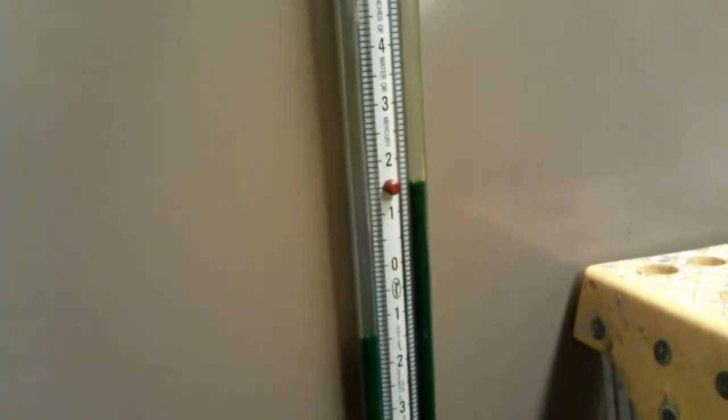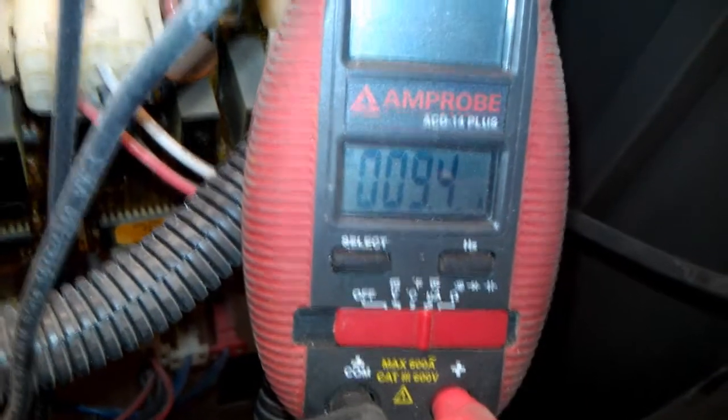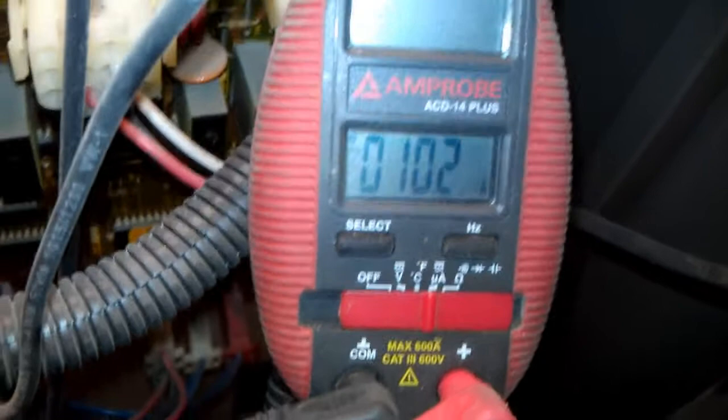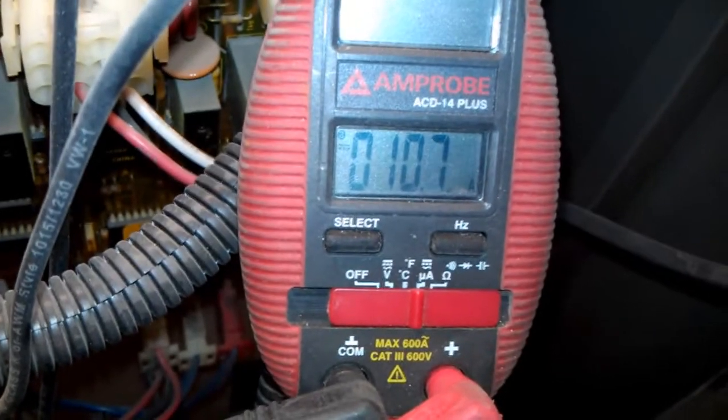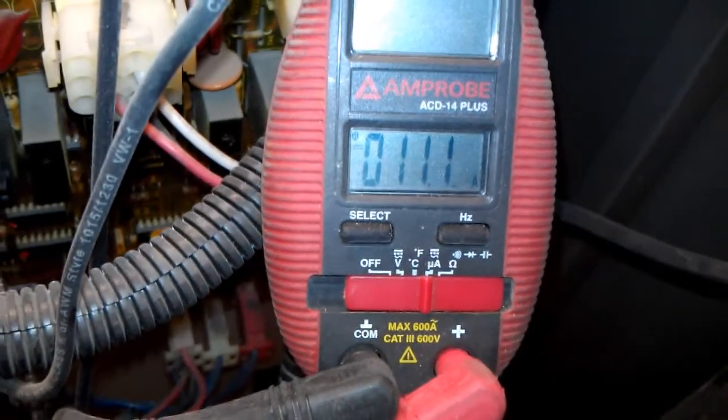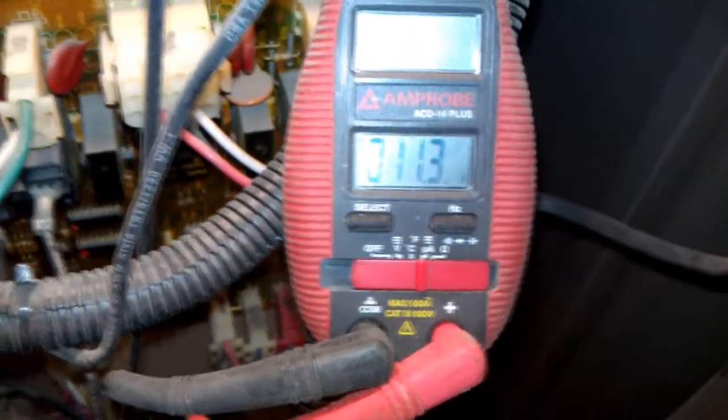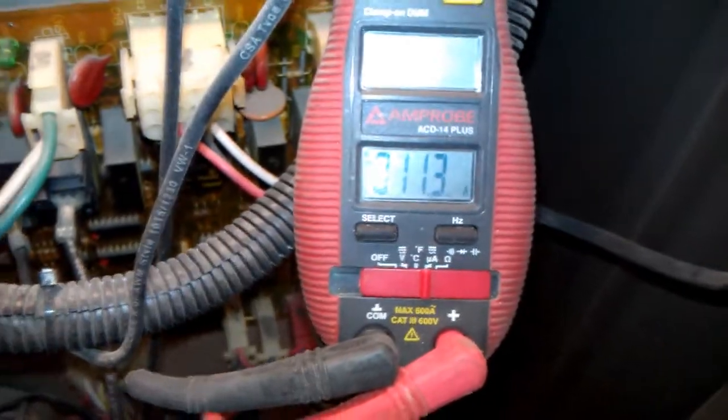Still at three inches of water column just like before. Almost ten microamps. There we go. Ten microamps. Do you see? Eleven now. The burner's about high. I already cleaned that flame sensor.